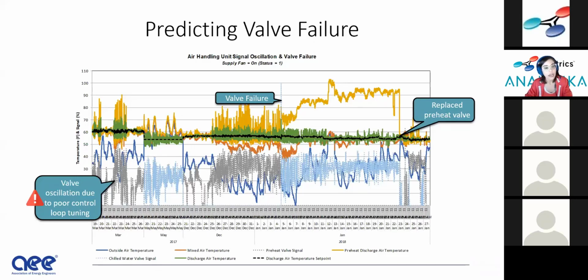This is a valve failure. Now, how do we predict a valve failure? We can look at the oscillation of the valve, right? You can also look at set points and say there's set point disagreement, and that can cause some of this too, and I'll show you how in a second. Now, this is a time series chart, so we have time on the bottom. That's what most of the charts shown today will look like. So we have March, May, December of 2017 here, and it goes on. And then this is our y-axis with temperature and valve signal. The gray here that's oscillating, that's the preheat valve signal, and the blue in the bottom, I'll use my mouse over here, that's the chilled water valve signal. The discharge air temperature is shown in green, and the discharge air temperature set point is shown in black.